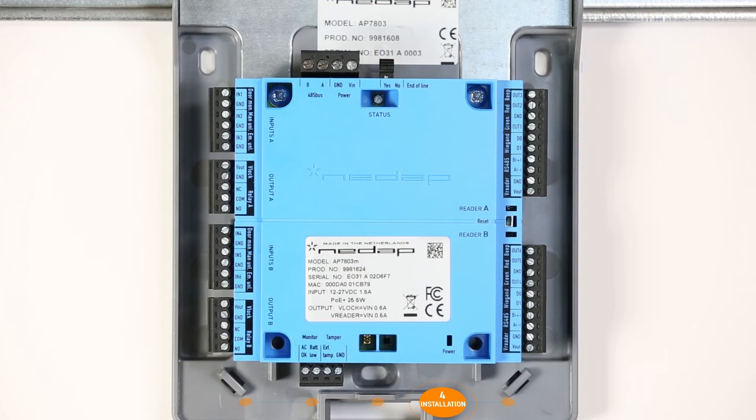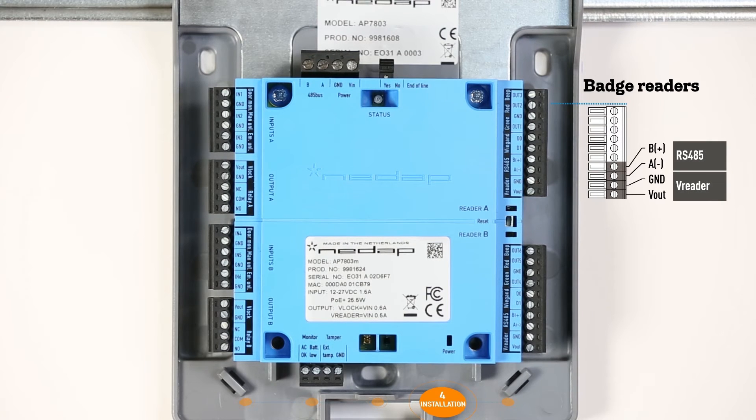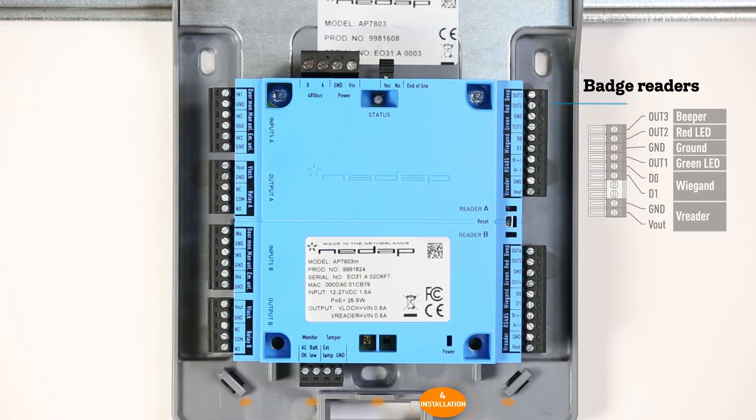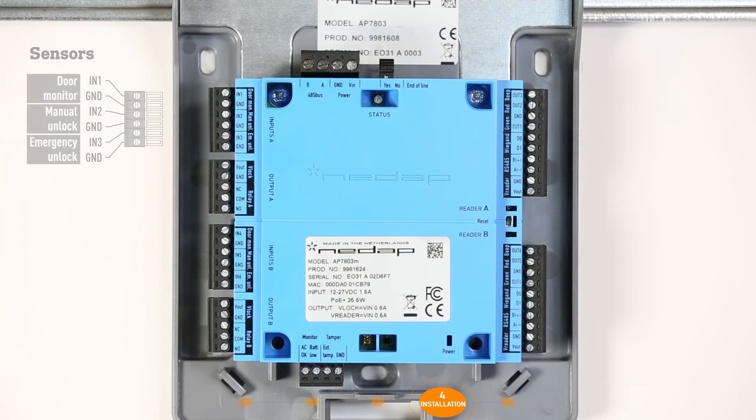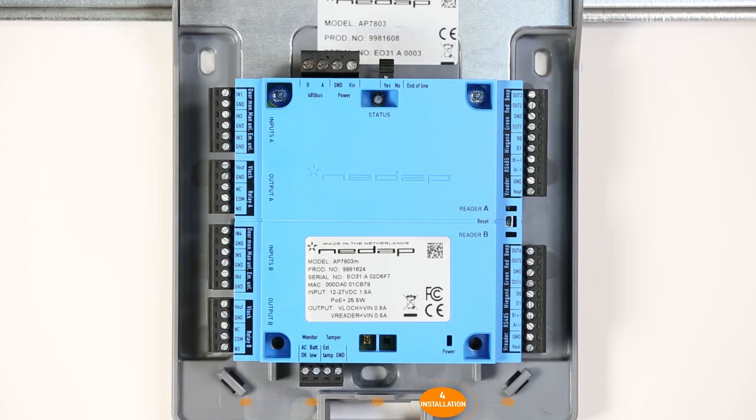After all of the devices have been mounted, it is time to connect the readers on the right side and the locks and sensors on the left. Up to two badge readers can be connected. The EOS Blue hardware line supports the RS-485 protocol for Nedap readers. In addition, the WIEGAND protocol is also supported. The lock can then be connected — make sure it is connected in accordance with the supplier's specifications. Then connect the sensor. Note for each device the readers, locks, and sensors used per connector and the door they control.